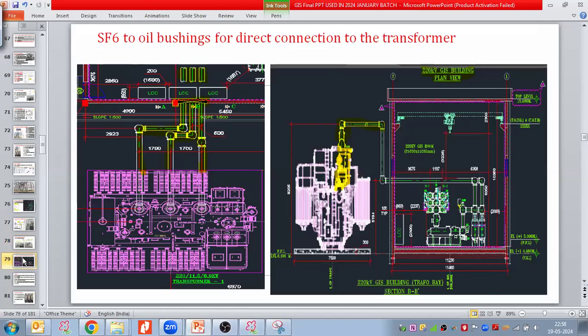If we have gas to oil bushing termination, which means in a few cases where the space is very limited, in those kinds of projects the GIS is directly connected to the bushing of the transformer. When space is not available, then you do this arrangement. When you have the space, do not do this arrangement. This arrangement is very costly. Try to avoid it if you have space. But if you don't have the space, this is the only option, then go with this option only.